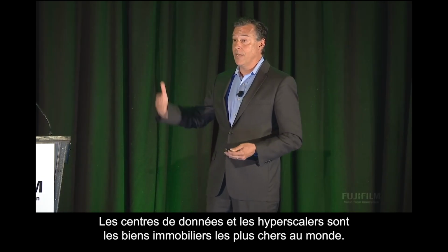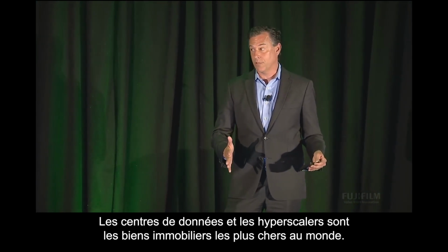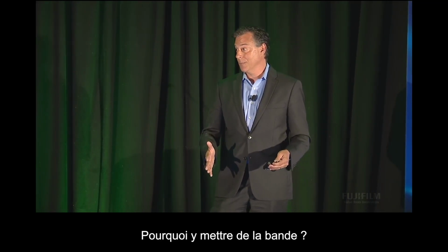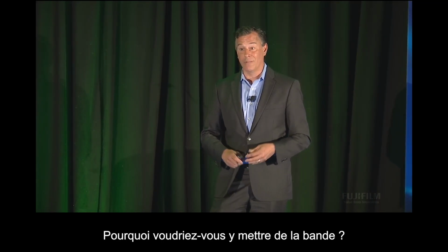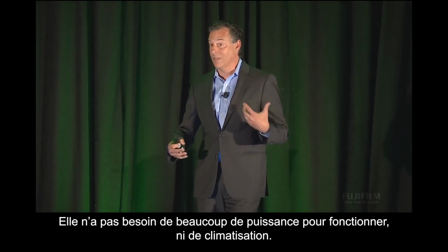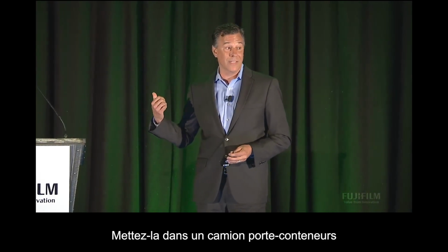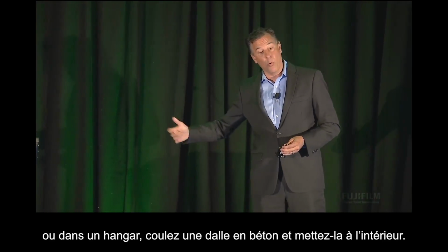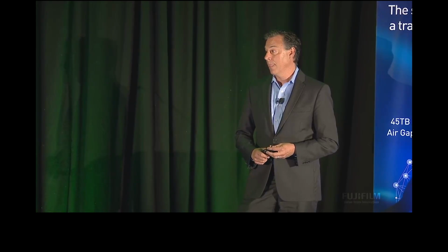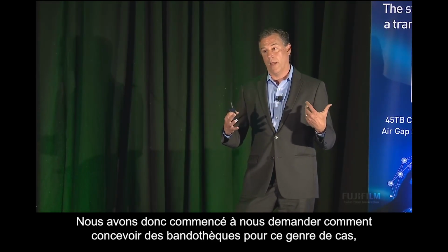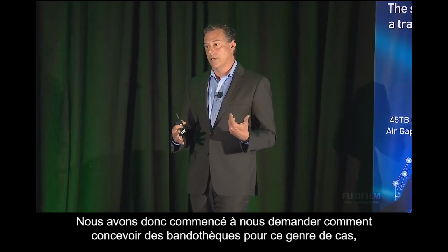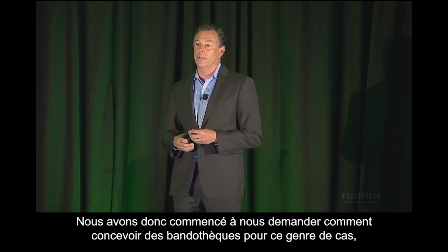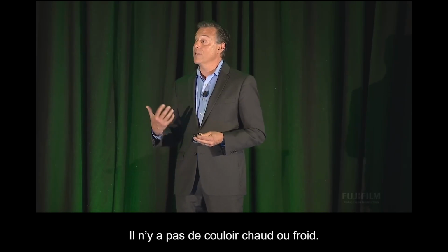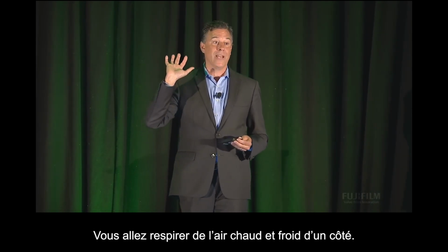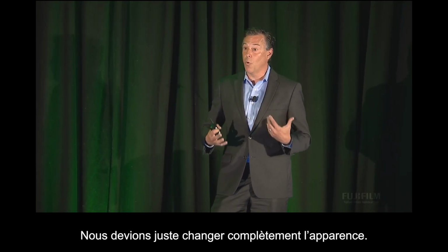Data centers in the hyperscaler are the world's most expensive real estate. Why put tape in it? Why would you ever put a piece of tape in it? Tape doesn't need a raised floor, doesn't need that heavy power, doesn't need that air conditioning. Stick it in a container truck. Stick it in a shed, pour a concrete pad and chuck it in there. So we started looking at, okay, how do we design tape libraries for that kind of a use case where you can't get to the front and back of it. There is no hot and cold aisle. You're going to respirate hot and cold air out one side. We just had to completely change what these things look like.